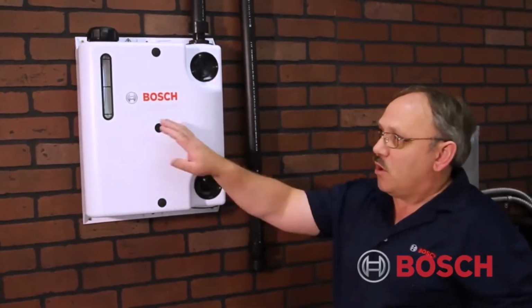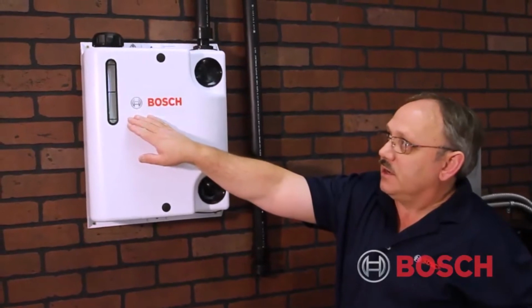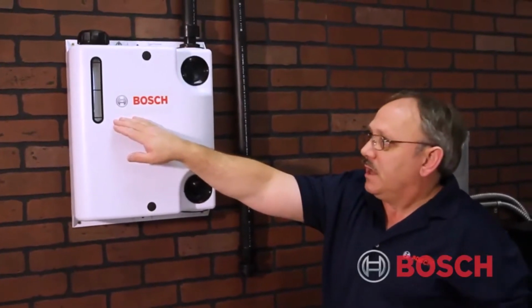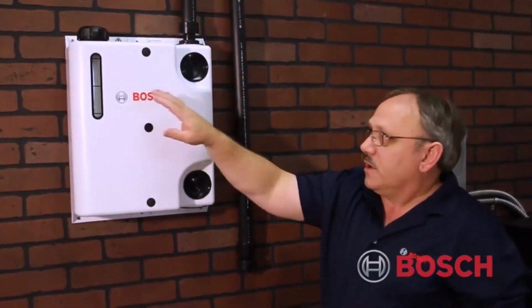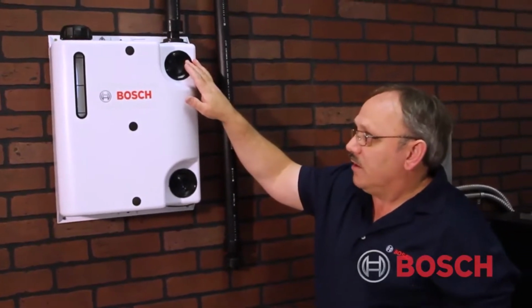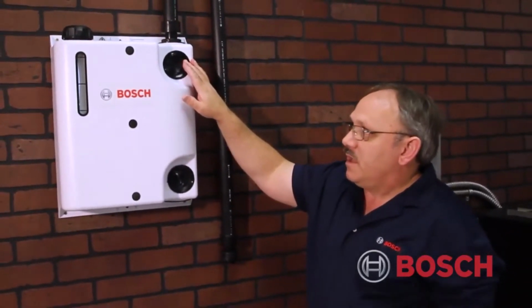It has a small reservoir on it, and you can see the sight glass here and a cap on top where you can add fluid to the system, as your pipe expands and contracts or as you require more fluid. Also has a set of isolation valves located on it so you can isolate it from the system while you are doing your flushing and purging processes.